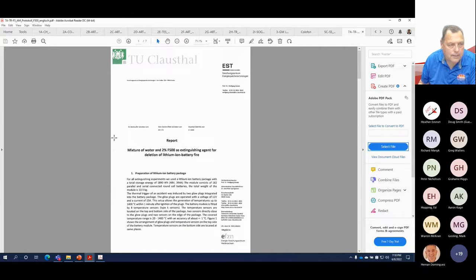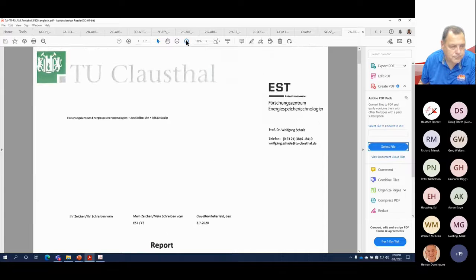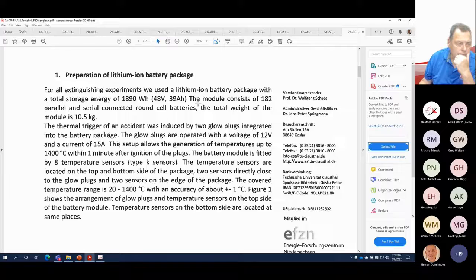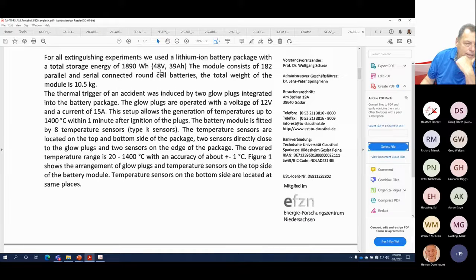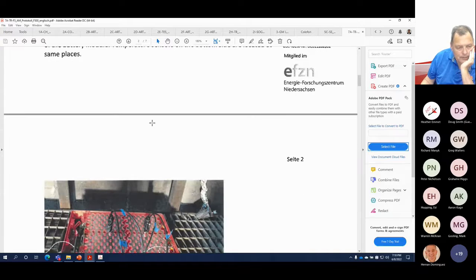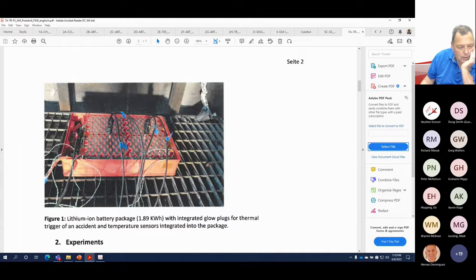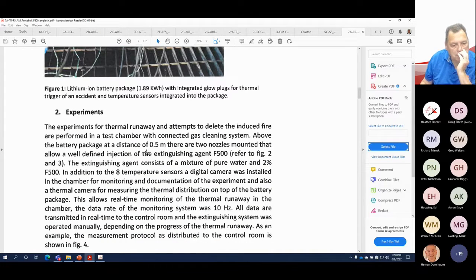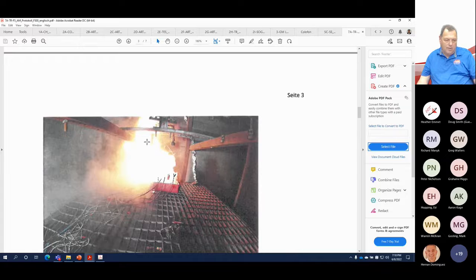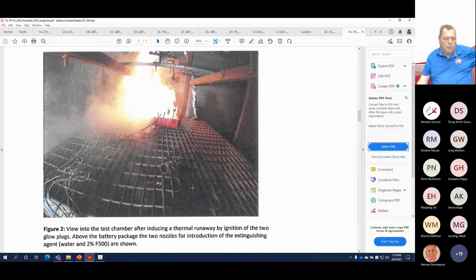One of the tests we ran, I think this is a significant test. Here we're taking a battery, very similar to what we did at Kiwa. We have a temperature range of sensors from 20 to 1400 C, and they actually topped out at 1400 C - so we're not exactly sure if it went above that. In this experiment, they put the batteries into thermal runaway, with 8 temperature sensors in place. The agent is being delivered through 2 mist-style nozzles at a 2% solution.